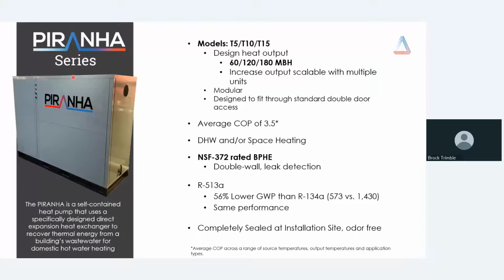So the Piranhas are designed for domestic hot water applications. With this, for complete potable applications, we have what is called an NSF 372 rated braze plate heat exchanger. This basically just means that the piece of equipment that interacts with the potable water itself is rated for drinkability, human consumption, etc. That's really a key to making sure that, especially because we're working with wastewater, we keep everything absolutely safe. Several layers of separation between the wastewater source that we're drawing energy from and the potable water that we're putting energy into. Now, the hot water, typically designed for domestic hot water, can also go into space heating or any other type of application that you may have. Really, the goal is just to recover that energy that would otherwise be thrown away and use it for hot water within your building space.